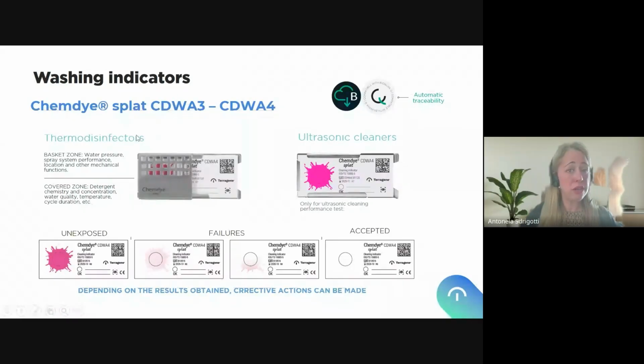Both of these indicators, even though the pictures show the pink one, the blue one is exactly the same use, and both can be used for thermal disinfection as well as ultrasonic cleaners. We have two different holders for this, because ultrasonic washers work in a different way, through cavitation. We will see that later. So we have to use the indicator in this holder, which does not have a front part to protect the indicator because everything will be submerged. Both of them have a clip at the back so that you can secure the indicator on the basket that you are going to use for monitoring.